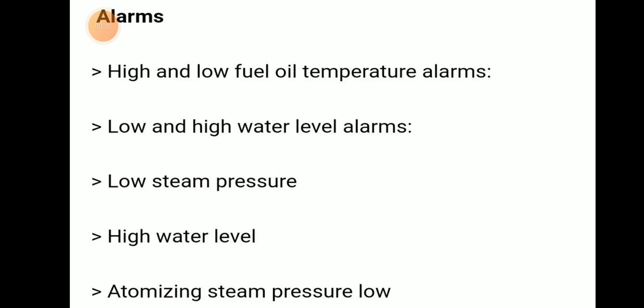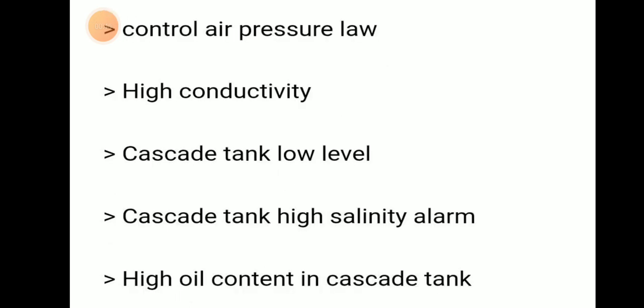So alarms include: high and low fuel oil temperature alarm, high and low water level alarm, low steam pressure alarm, atomizing steam pressure low alarm, controlled air pressure low alarm, high conductivity alarm, cascade tank low alarm, cascade tank high salinity alarm, and high oil content in cascade tank alarm.